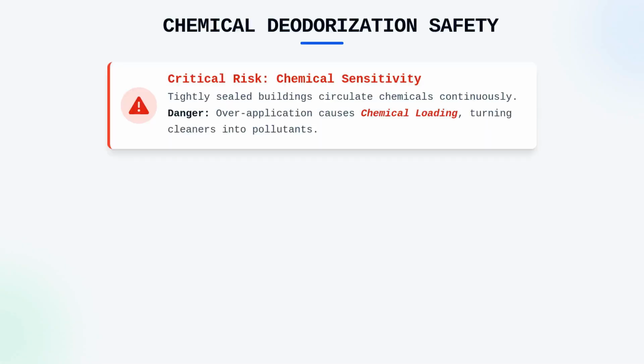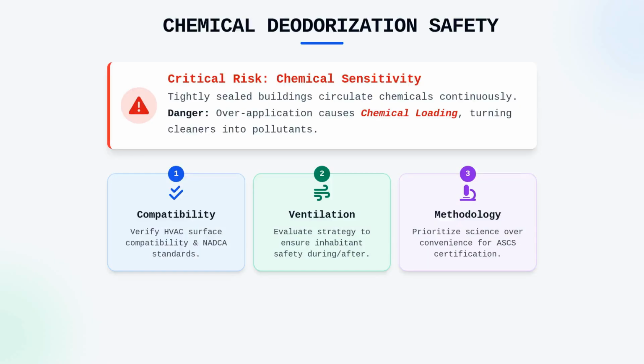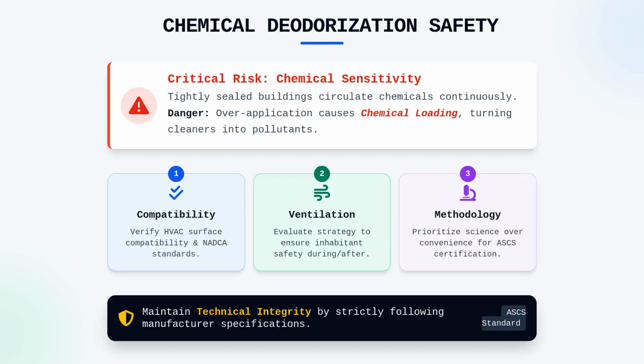You must remain acutely aware of the risks associated with chemical sensitivity among building occupants when choosing your deodorization agents. Many modern buildings are tightly sealed, meaning that any chemical introduced into the supply air will circulate until it is eventually filtered out or exhausted. You should only utilize products that are compatible with HVAC system surfaces and verify that they are applied in accordance with manufacturer specifications and NADCA standards. Over-application can lead to chemical loading, where the cleaner itself becomes an indoor air quality pollutant that causes more distress than the original odor. Always evaluate the ventilation strategy during deep cleaning to ensure the environment remains safe for inhabitants during and after the process. By prioritizing scientific methodology over convenience, you maintain the technical integrity required for ASCS certification.